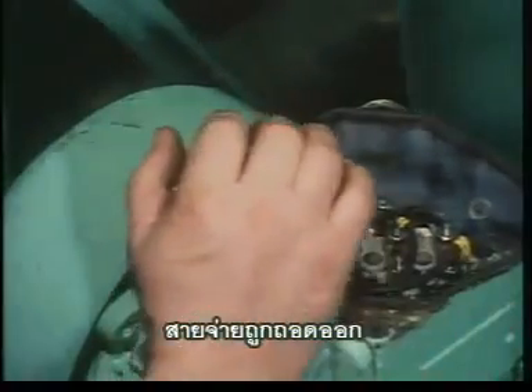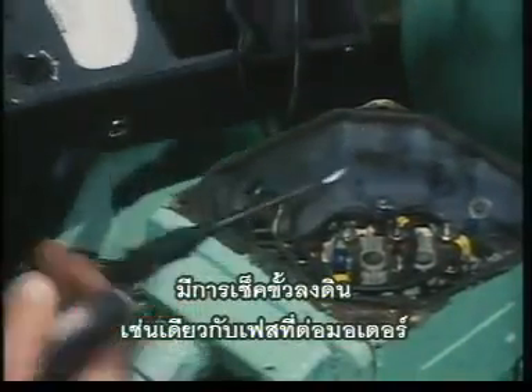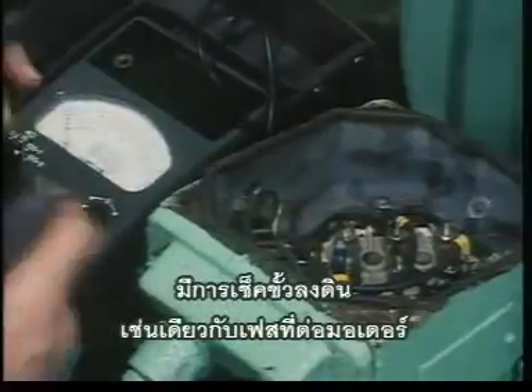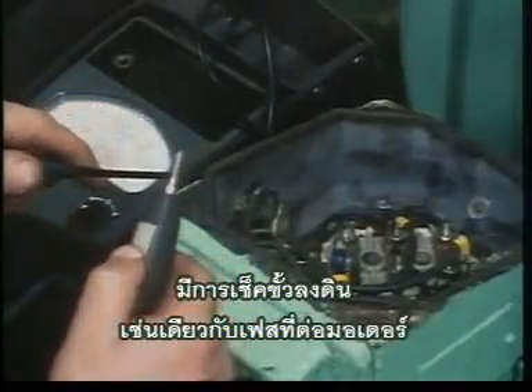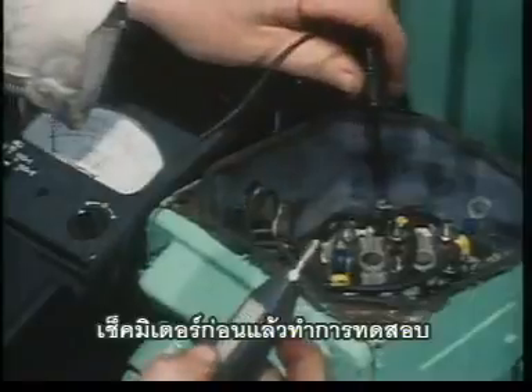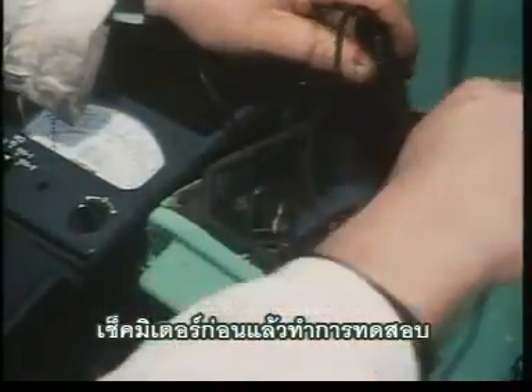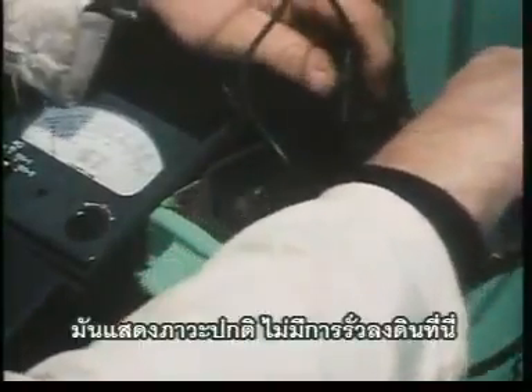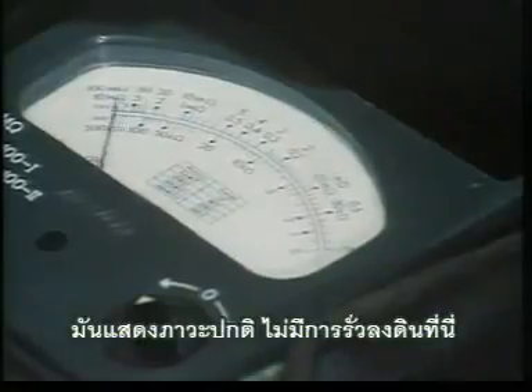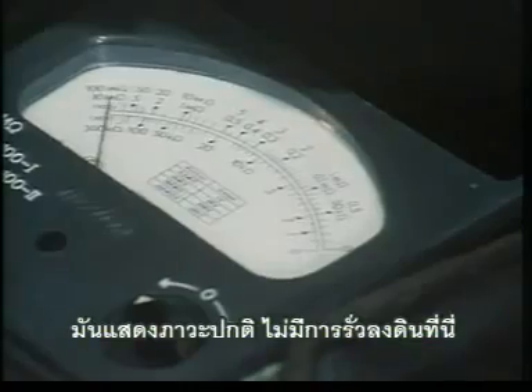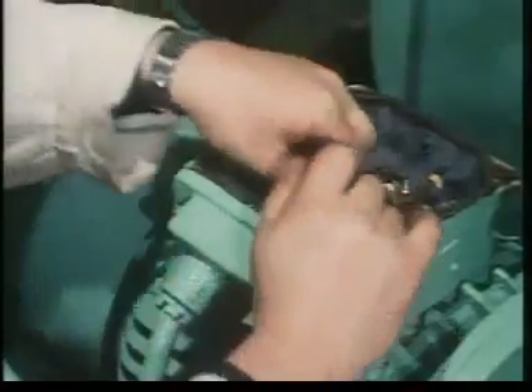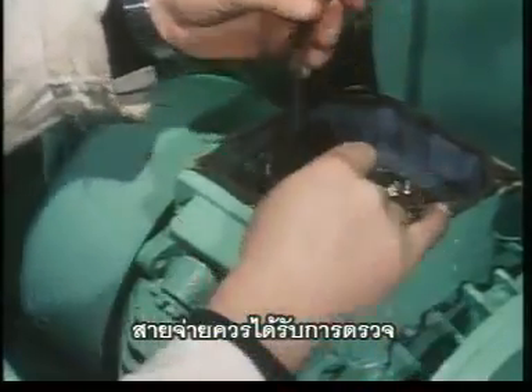The feeder cables have been disconnected. Now the terminals are checked to earth as well as the phase windings of the motor. The meter is checked first, then the test is made. This shows normal condition, no earth fault appears there. The feeder cables must now be examined.